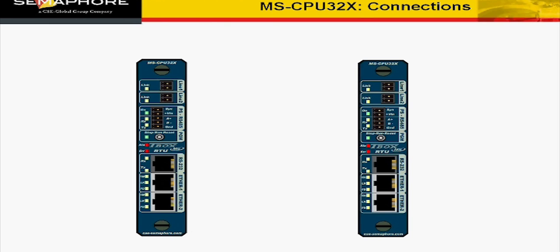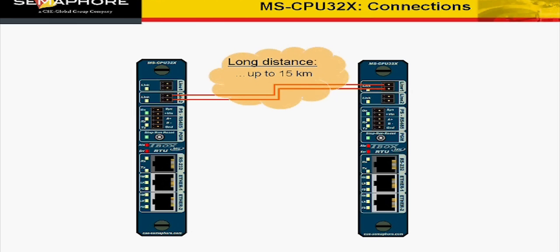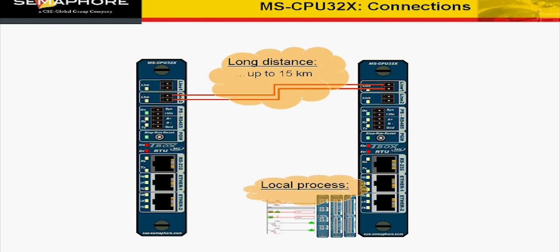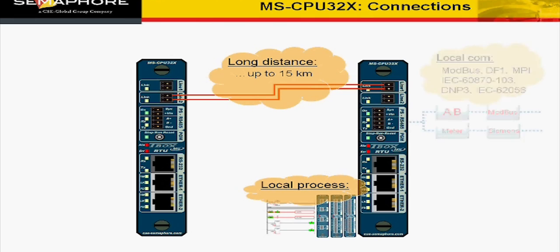To illustrate the possible communication, let's use two MS-CPU32X. SH-DSL modems allow connection up to 15 km through a pair of cables. Each CPU has its local process controlling I/O through ladder or BASIC. Each CPU has local communication to field devices or existing equipment in Modbus or other standard protocols.